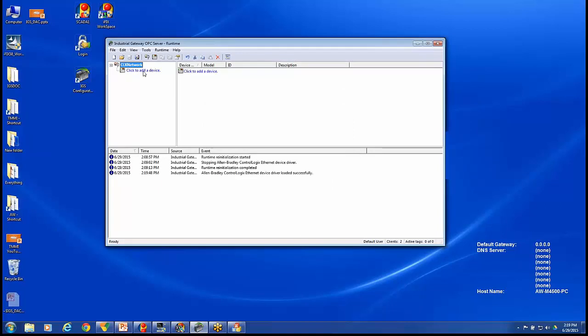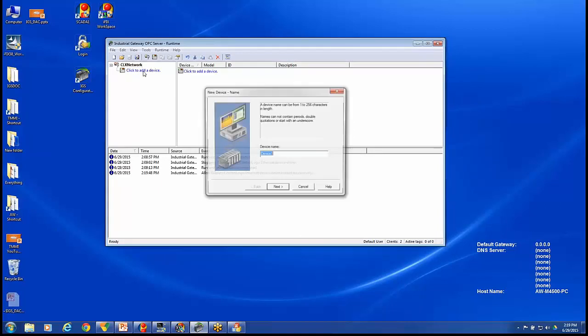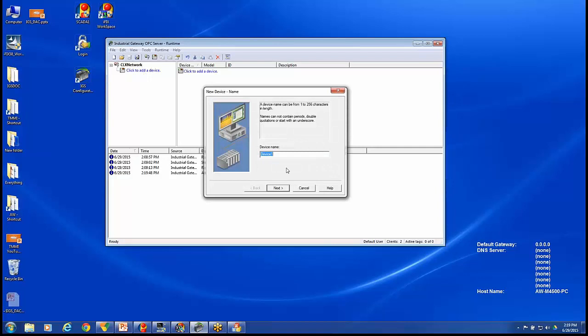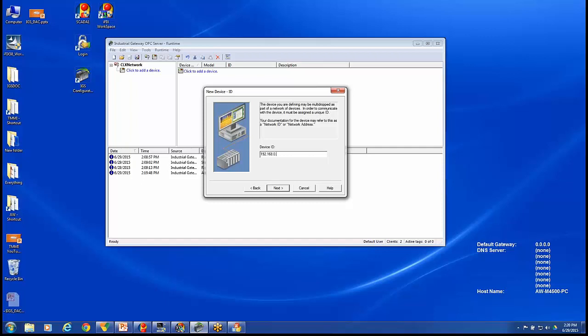Next we want to add our device. I'll call mine CLX PLC. It is a ControlLogix 5500. There are other options for you based on the hardware you're using. We are using ControlLogix 5500. This will be my device ID. That is the IP address with the network adapter and CPU slot. So mine is 192.168.0.11, 1, 0.